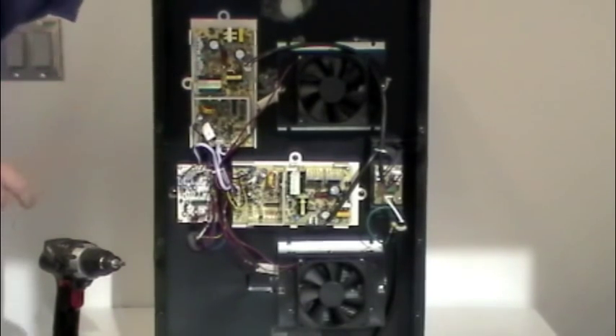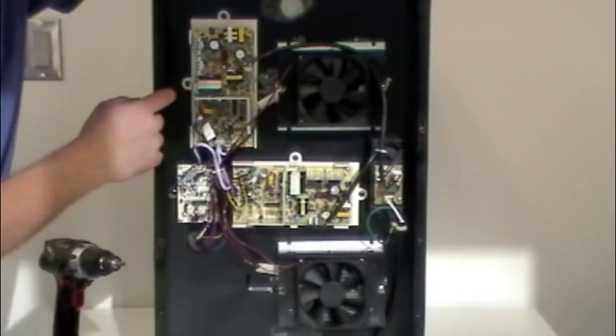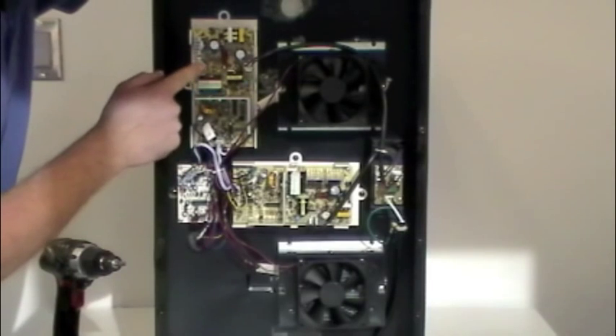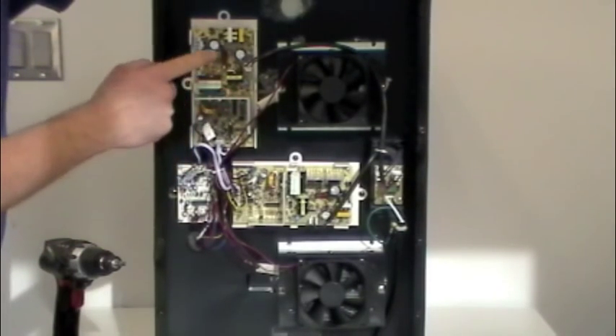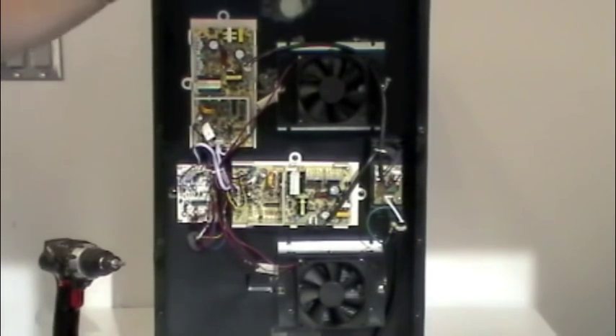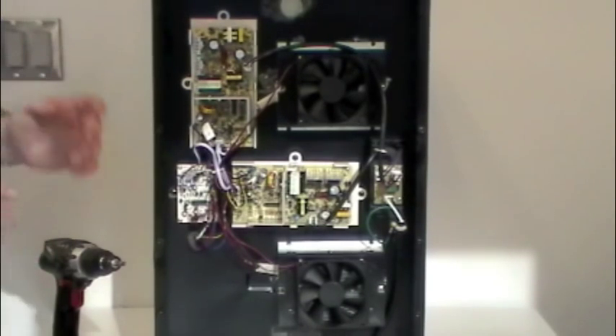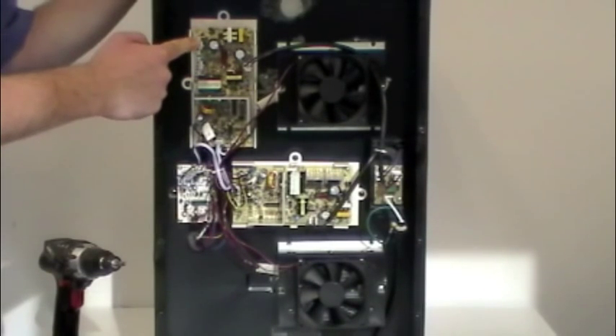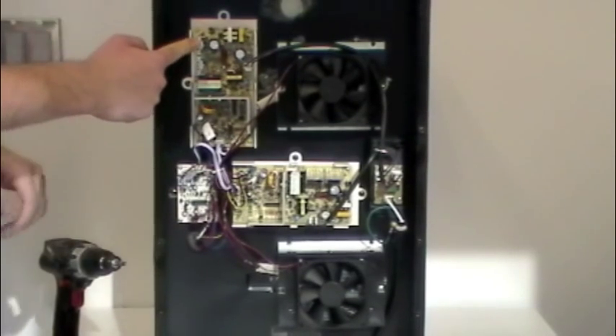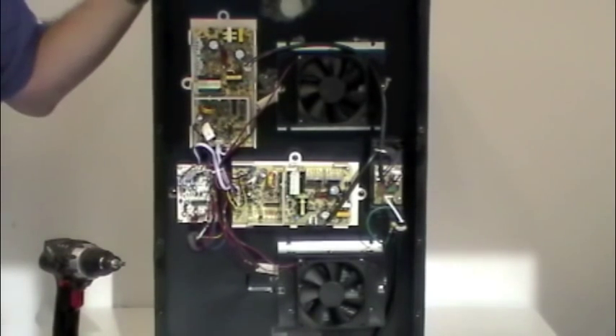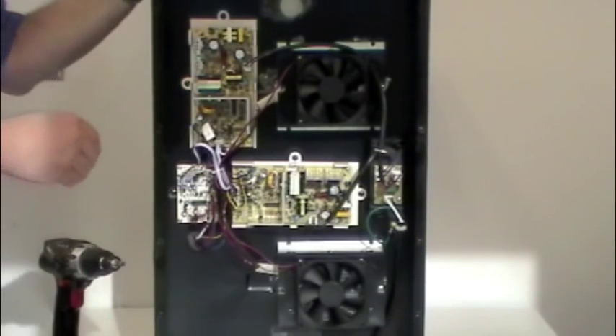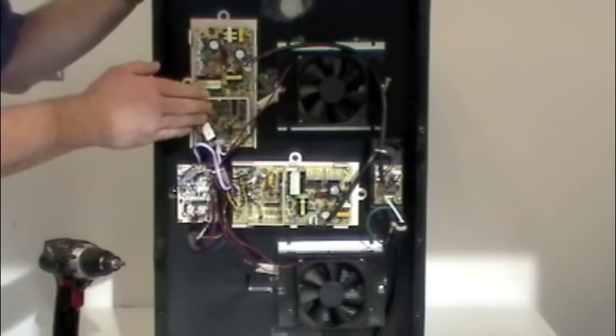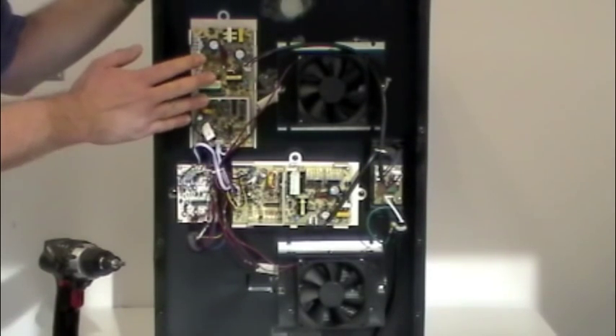There are some things you may do with it powered on. I told you in the beginning to make sure the unit's unplugged, but obviously, there are things that we need to do with the unit plugged in. And I will tell you that if you look here, these heat sinks here and this one, both of these here, they actually have a transistor that's actually sealed to them with some conductive grease. And I will tell you from personal experience, if you hit one of those, please don't have your hand on this cabinet. Because if I hit that, I'm running a couple amps through me and it's going right through my heart. I'm dead as a doornail. So, make sure that you're not touching this cabinet. If you do bump one of those, please be very careful. The reference voltage on those is about 300 volts DC. That's no joke. These provide a grounding path. And of course, they complete the circuit. But if this unit's powered on, please don't touch either one of these. Very, very important. Your life depends on it.